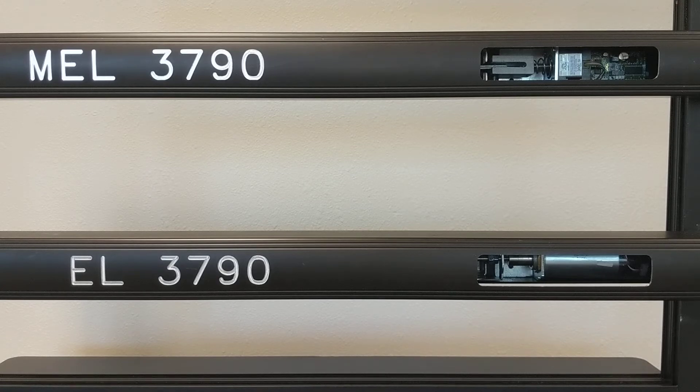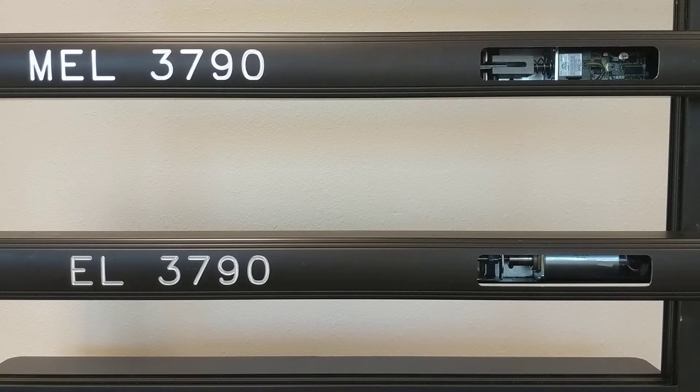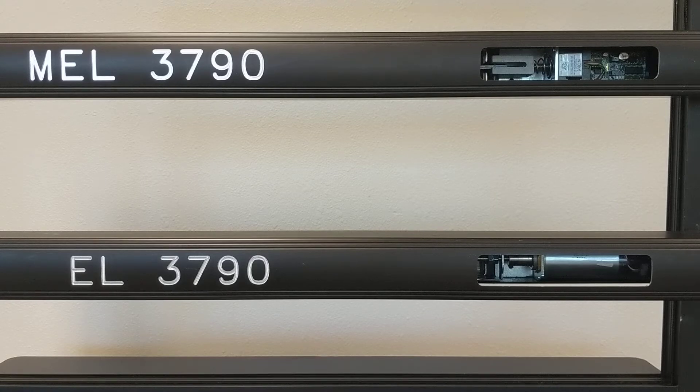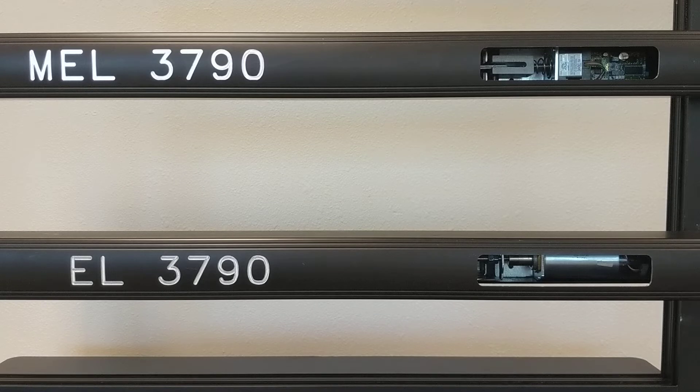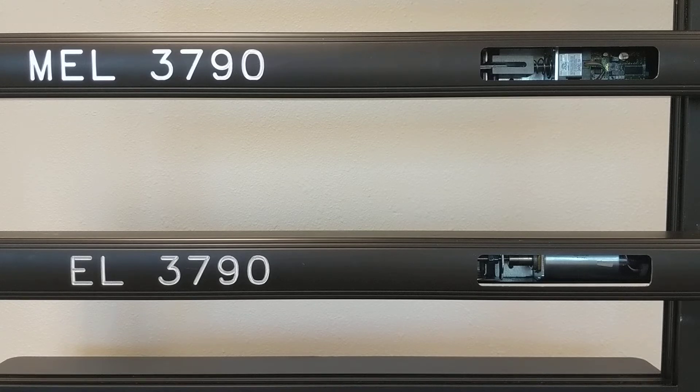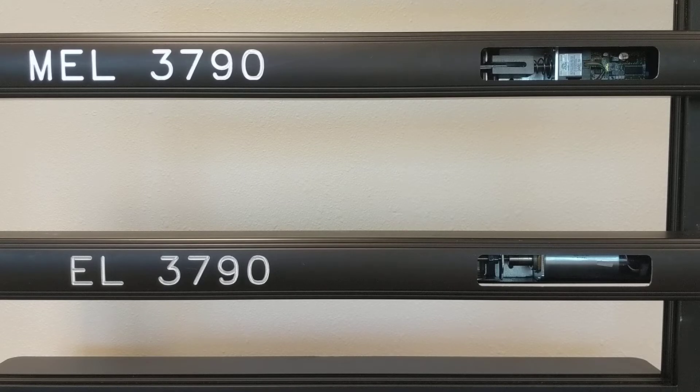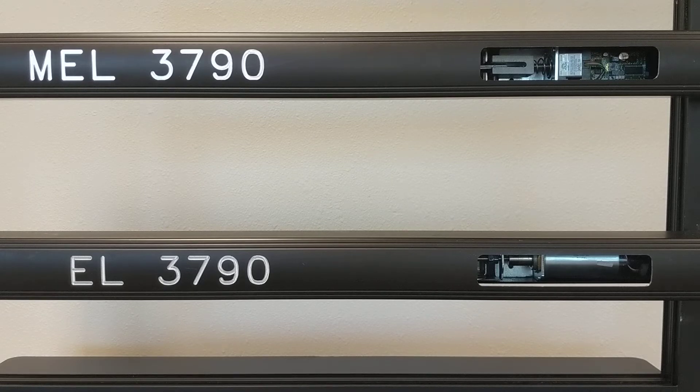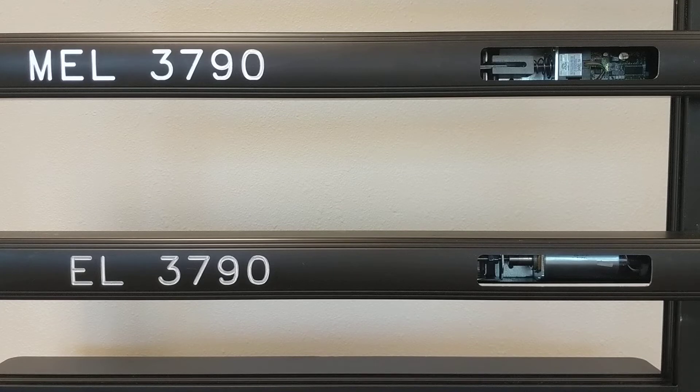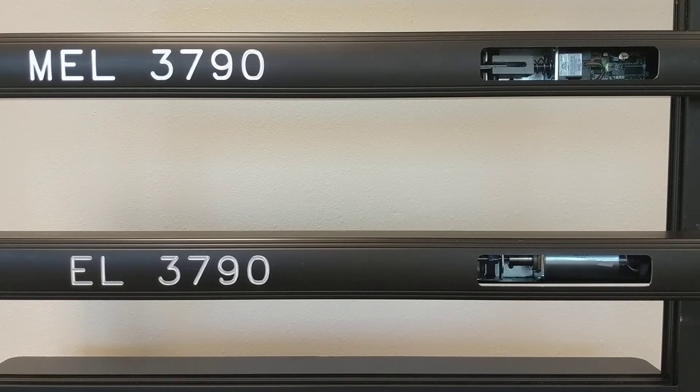The EL on the bottom requires a special power supply, either a PSEL-1500 for a single-door power supply, or a PSEL-3000 for a double-door power supply. This is a 16-amp power supply. The solenoid requires 16 amps of inrush in the first 300 milliseconds to be able to operate properly.